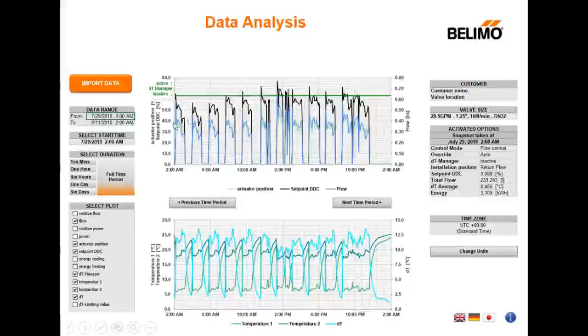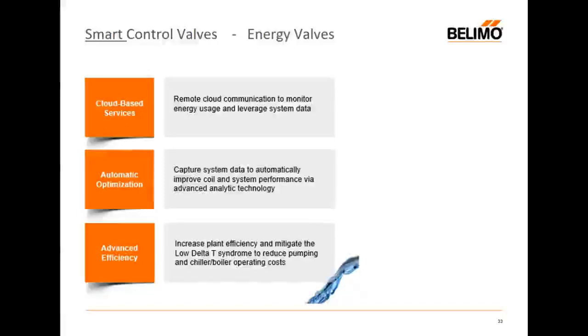I can track the actuator position in relation to the flow to check that the system is operating healthily. I can check the supply temperature to make sure it's being maintained. The delta, the return temperature. All of these elements are possible to harvest, gather them in and date stamp them and use them to the benefit of the system. But if I use smart control valves, I need to be able to leverage their capabilities. And so remote cloud communication is just one way we can do that. Another, of course, is data capture, whether it's onboard or onboard and shared. It's important that I'm able to analyze what's gone on in order to improve it and continue to improve it.